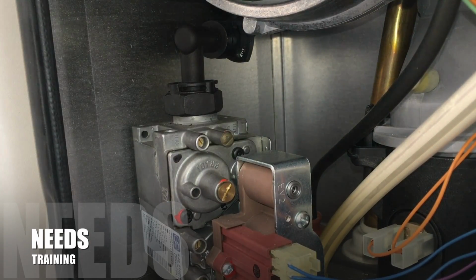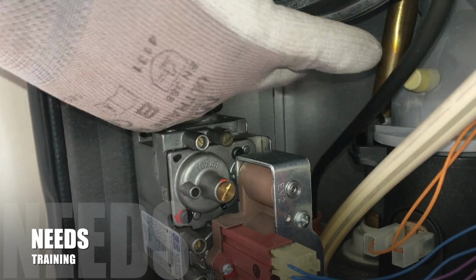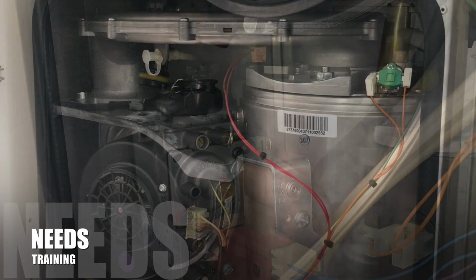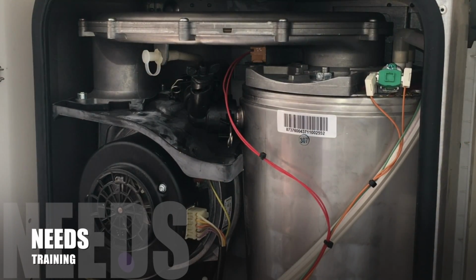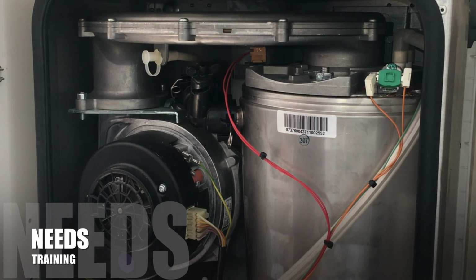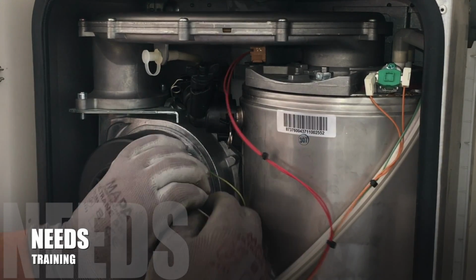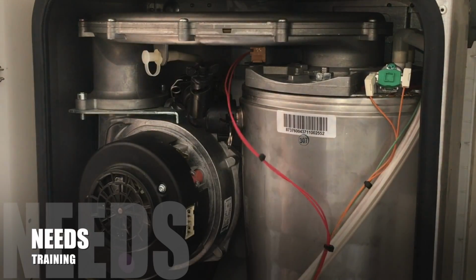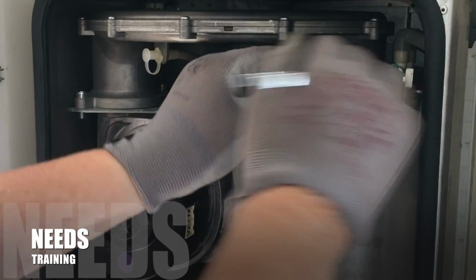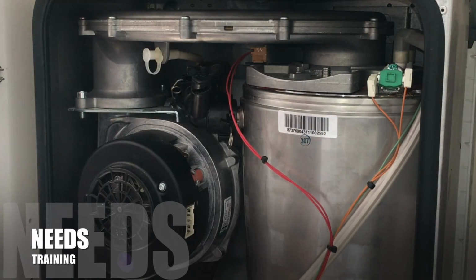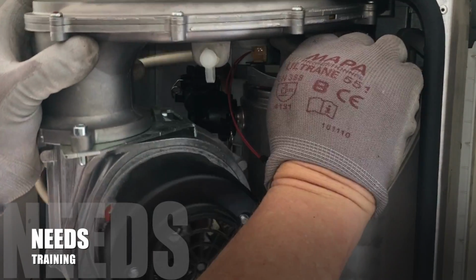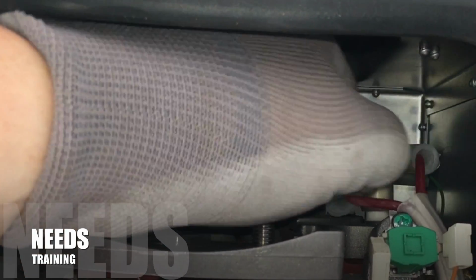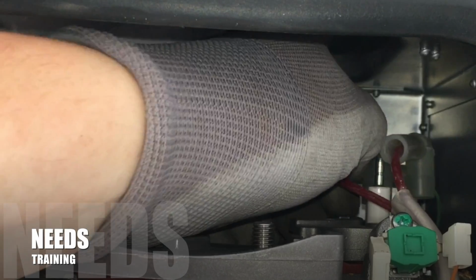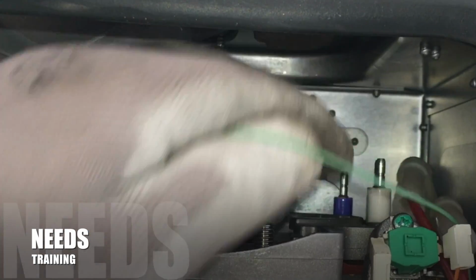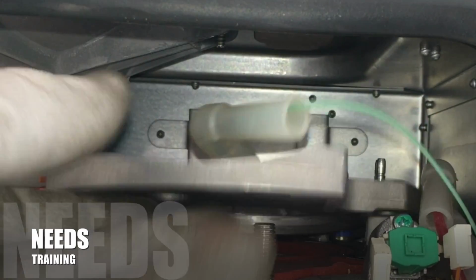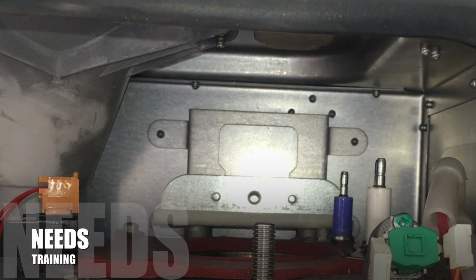Remove the gas tube from the gas valve. Remove the fan protection plate and disconnect the fan from the harness. Using a 13mm spanner, remove the clamping plate nut. Now you can remove the gas manifold and the fan. Disconnect the HT harness connection and the flame rectification connection from the electrodes. Remove the electrode for cleaning.